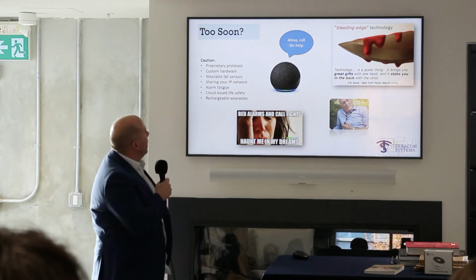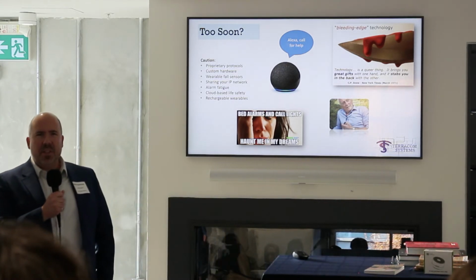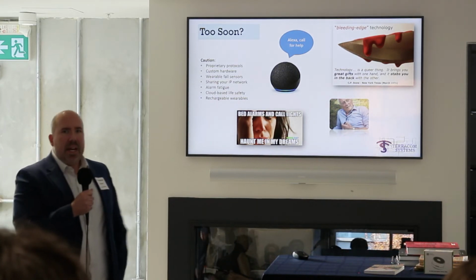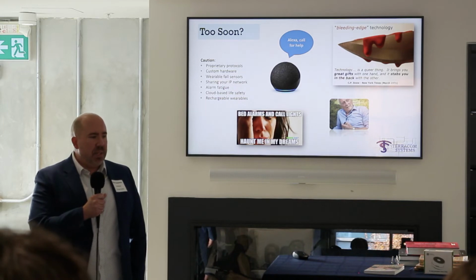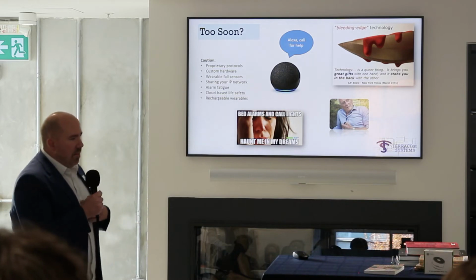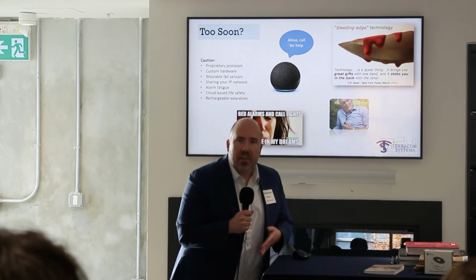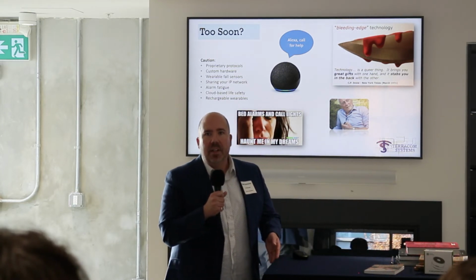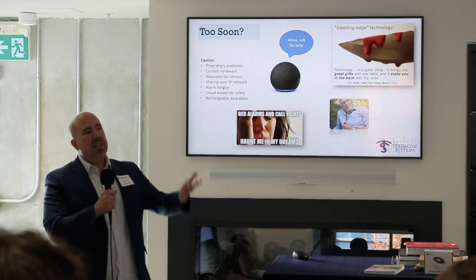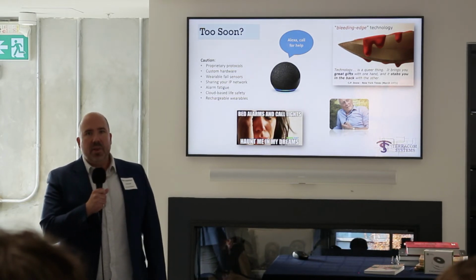One thing I also ran into: I was one of the first adopters of wearable fall sensors. I don't know if any of you have wearable fall sensors in your sites. They're more rare, but I adopted those early on, and I had some issues, because basically it would be like an oversized pendant that a resident would wear. Let's say I'm Mary Jones and I go up to my countertop. If my pendant just hits the countertop, that would trigger a false alarm, like I fell. If I'm Bob Smith wearing my pendant and I plop myself down on my Lazy Boy to watch the game, that would trigger a false alarm. If I even sit on the toilet, that would trigger a false alarm.